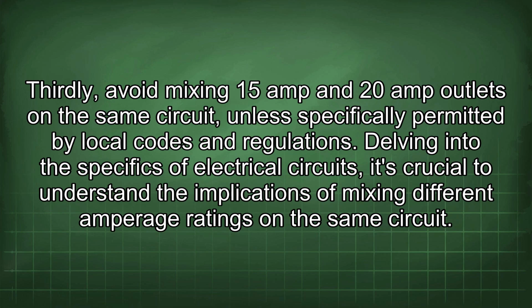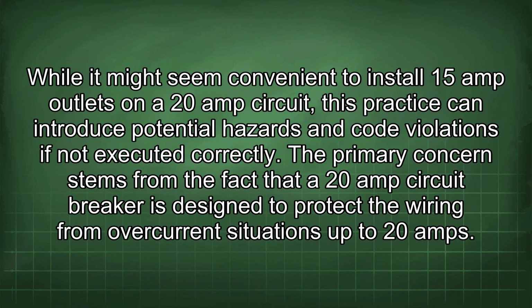Delving into the specifics of electrical circuits, it's crucial to understand the implications of mixing different amperage ratings in the same circuit. While it might seem convenient to install 15 amp outlets on a 20 amp circuit, this practice can introduce potential hazards and code violations if not executed correctly. The primary concern stems from the fact that a 20 amp circuit breaker is designed to protect the wiring from overcurrent situations up to 20 amps.